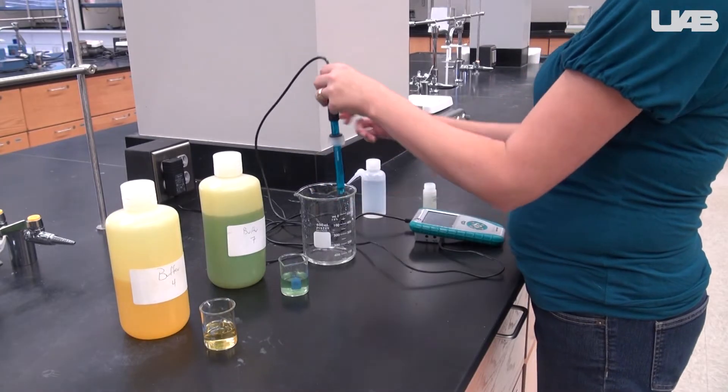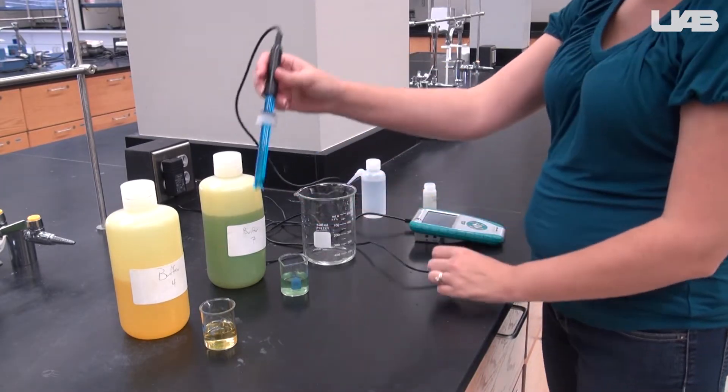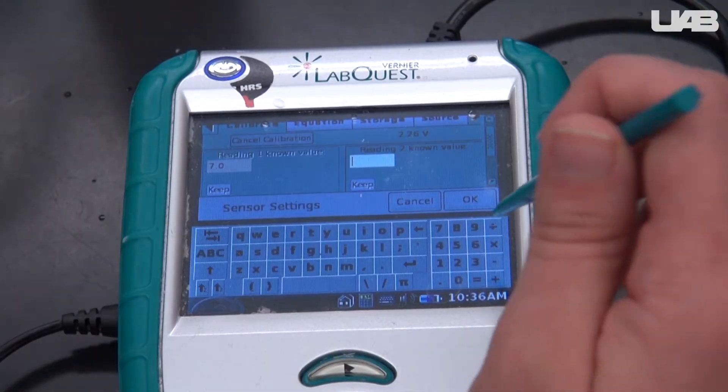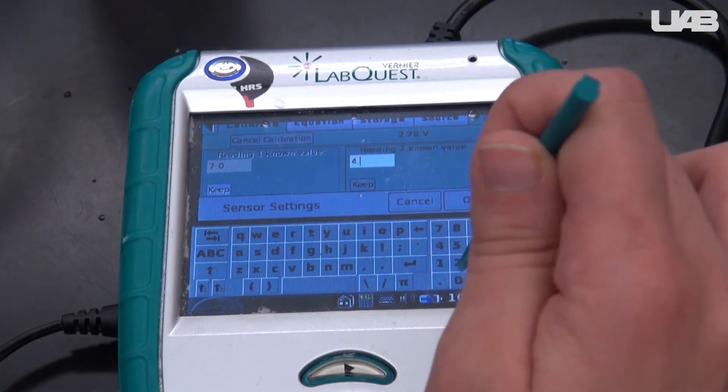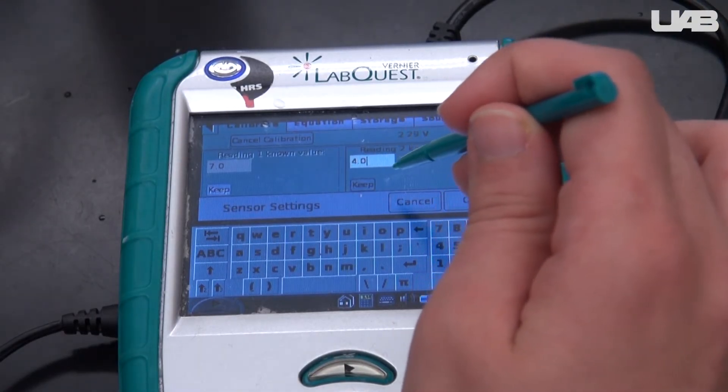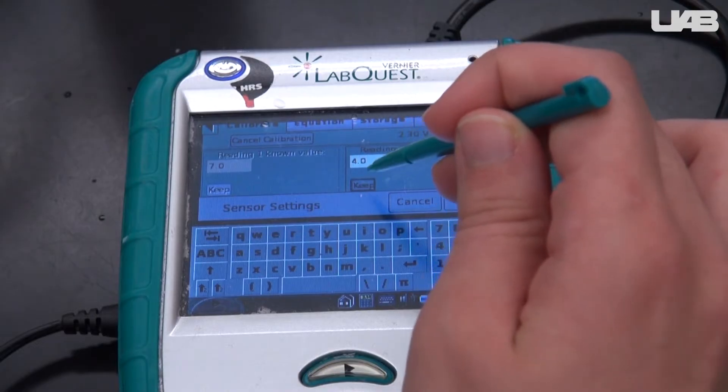Then rinse the probe off with the wash bottle and place it into the pH 4 buffer. Once the voltage stabilizes, enter 4.0 into the space and select Keep, then press OK.